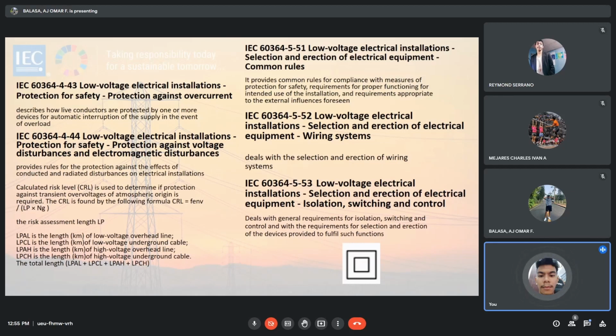Sabi dito, the total length is limited to 1 kilometer or by the distance from the first overvoltage protective device installed in the power network to the entrance of the installation, whichever is the smaller. If the distribution network's lengths are totally or partially unknown, then LPAL shall be taken equal to the remaining distance to reach the total length of 1 kilometer.